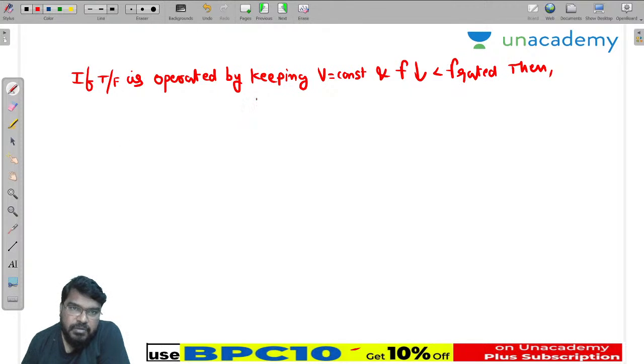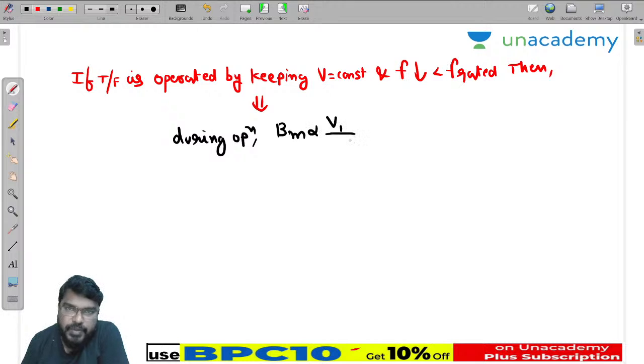We know that during operation, B maximum is directly proportional to V1 by F ratio. So by keeping voltage constant, if frequency is reduced below its rated value, the maximum flux density of the core increases.